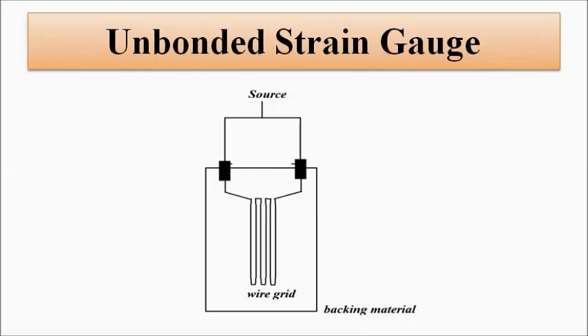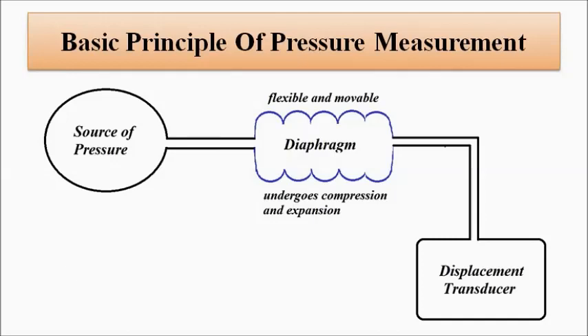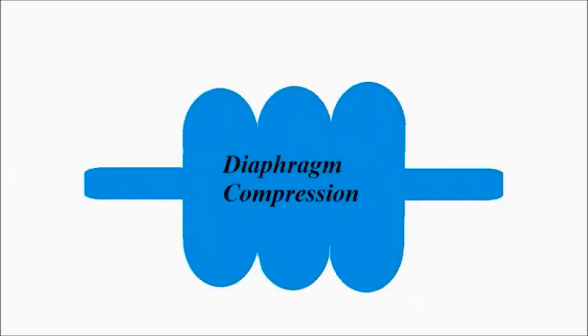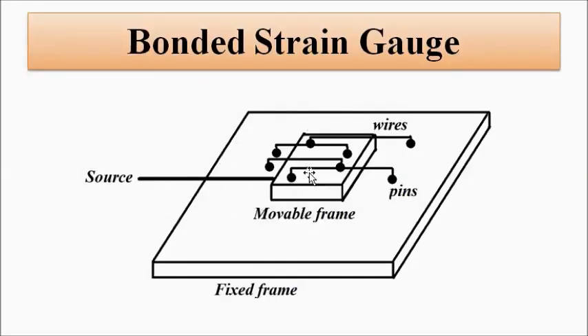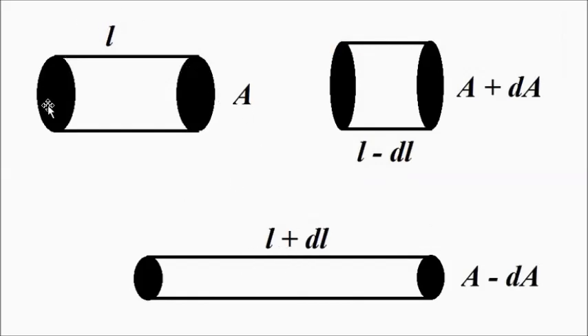When pressure fluctuations happen, the diaphragm undergoes expansion and compression. As a result, the movable frame in the bonded strain gauge moves left or right, causing the wires to get stretched or compressed. They can either elongate or compress. Suppose a wire in its original form undergoes expansion — it elongates, so there will be an increase in length by a margin dL and a reduction in area by a factor of minus dA. Similarly, if it undergoes compression, length decreases by a factor of minus dL and area increases by a factor dA.